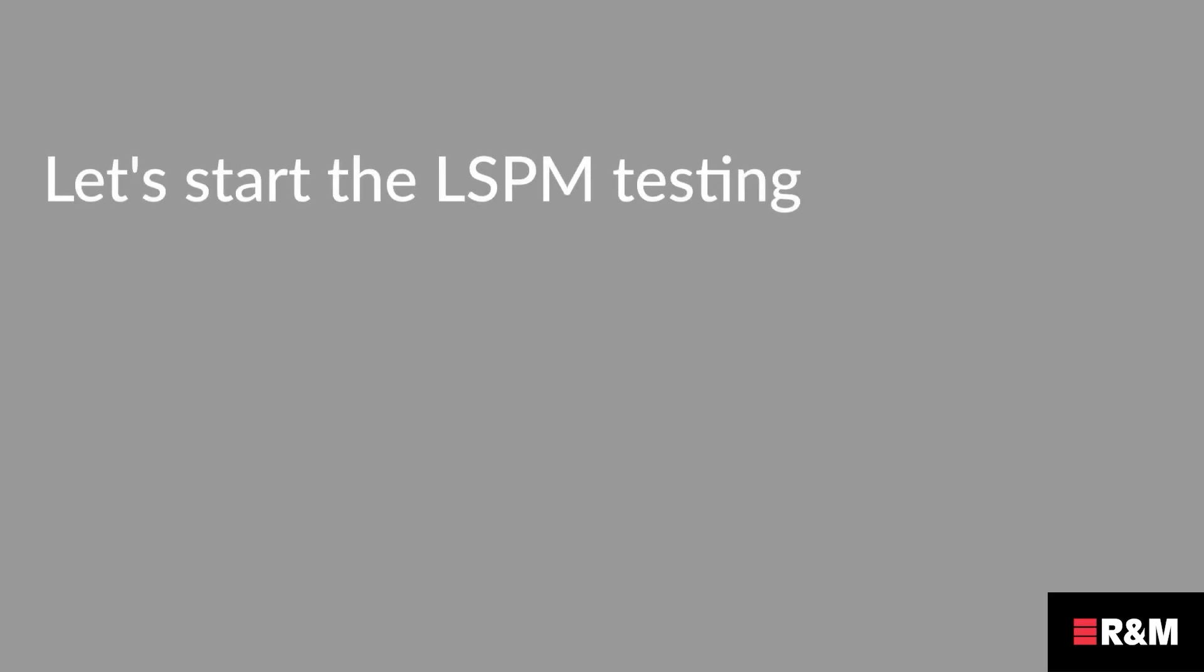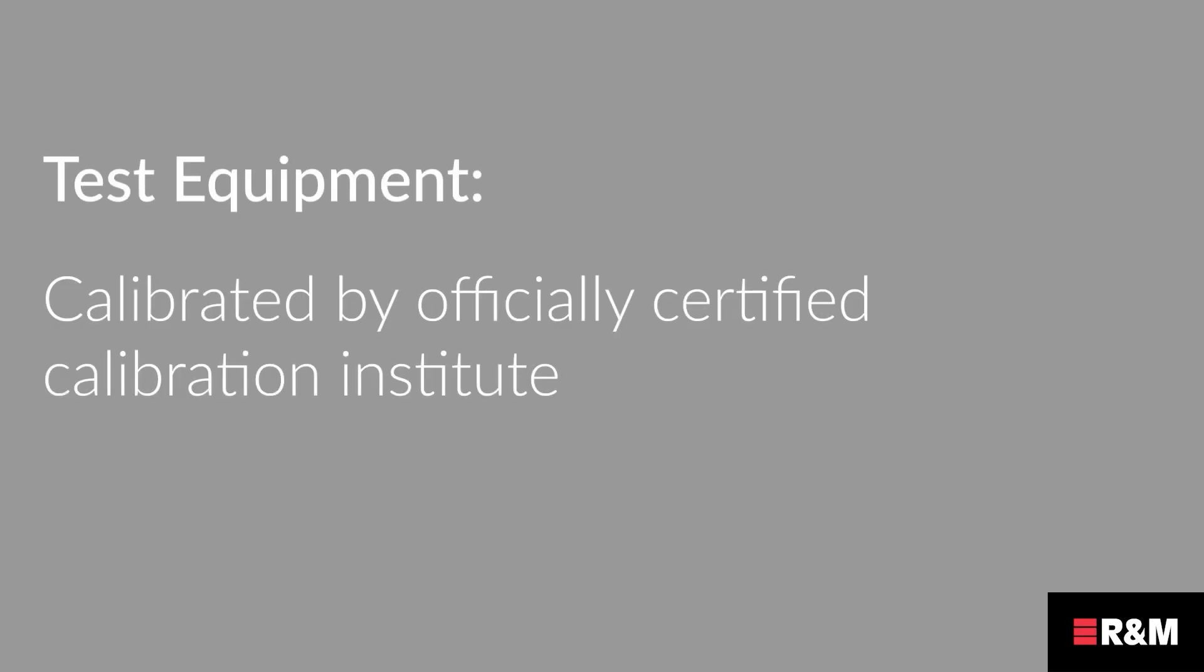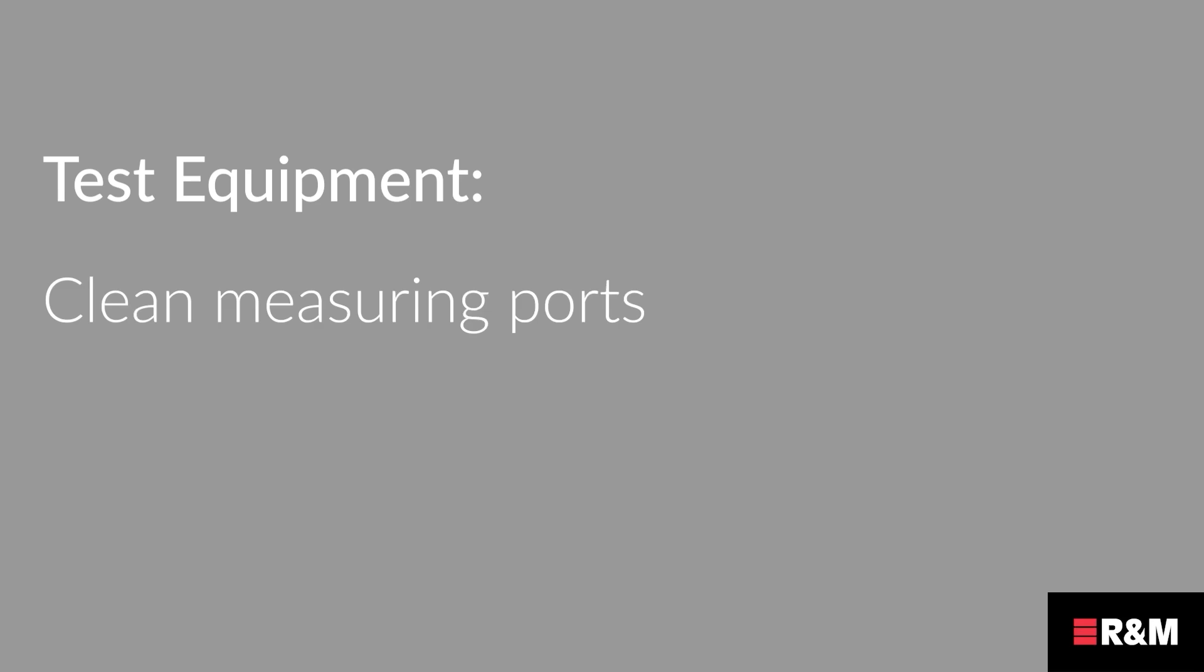Let's see the LSPM tester and test equipment. In order to be able to get valid measurements, the test equipment must be calibrated by an officially certified calibration institute according to the equipment manufacturers guidelines. It must have clean measuring ports, good battery levels or a direct power supply, and must be acclimatized to the environment where it will be used.